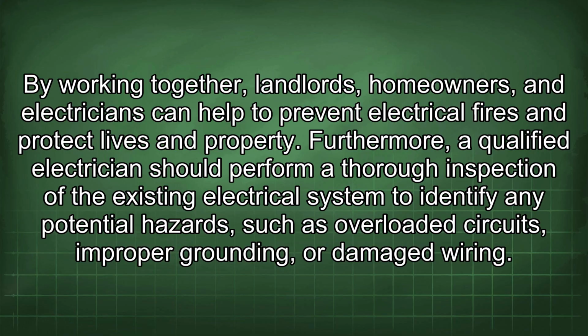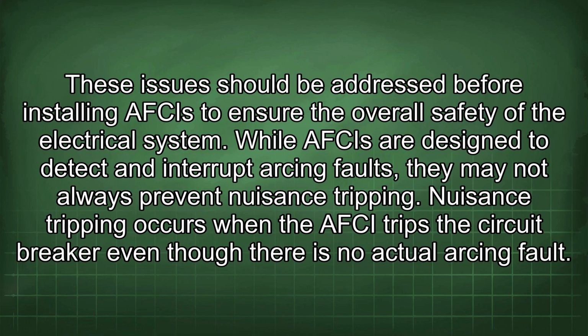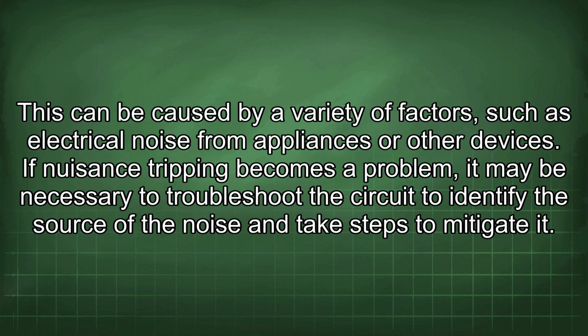Furthermore, a qualified electrician should perform a thorough inspection of the existing electrical system to identify any potential hazards, such as overloaded circuits, improper grounding, or damaged wiring. These issues should be addressed before installing AFCIs to ensure the overall safety of the electrical system. While AFCIs are designed to detect and interrupt arcing faults, they may not always prevent nuisance tripping. Nuisance tripping occurs when the AFCI trips the circuit breaker even though there is no actual arcing fault. This can be caused by a variety of factors such as electrical noise from appliances or other devices. If nuisance tripping becomes a problem, it may be necessary to troubleshoot the circuit to identify the source of the noise and take steps to mitigate it.